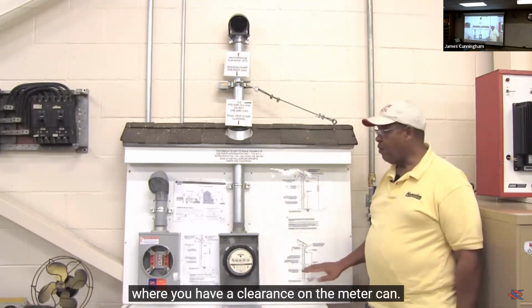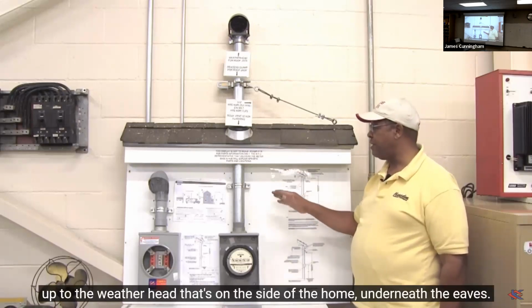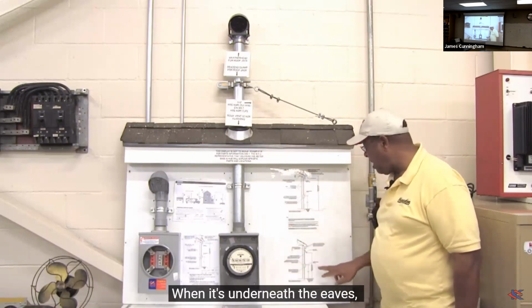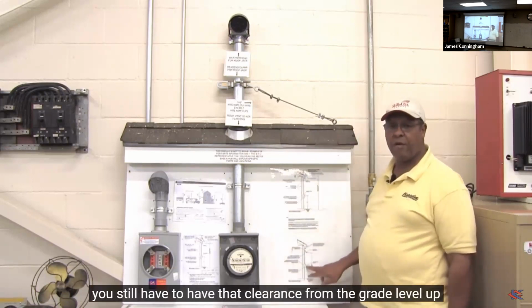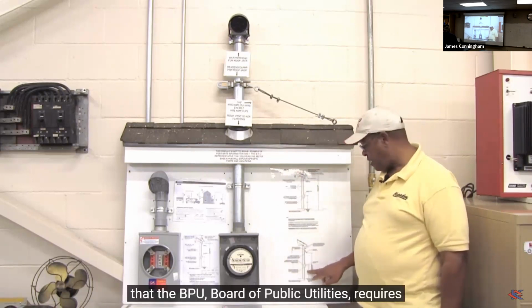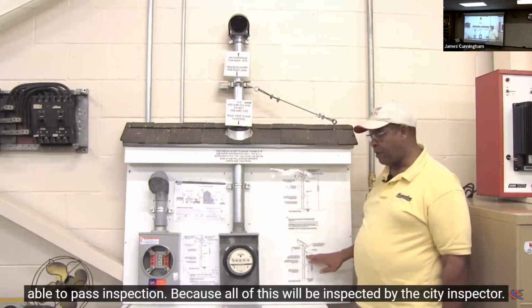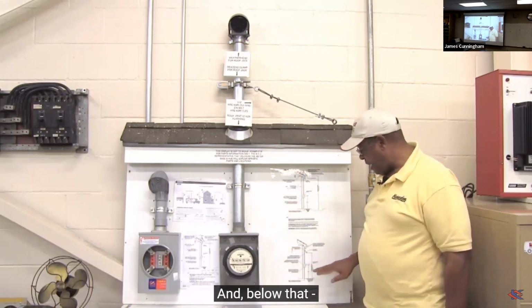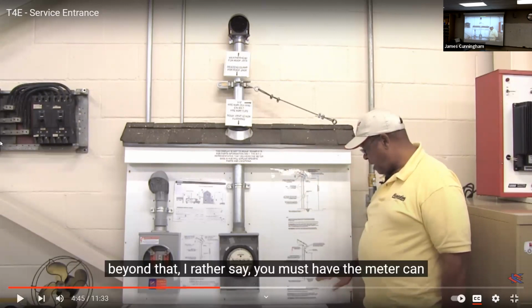Below here, you have a different setup where you have a clearance on the meter can up to the weatherhead that's on the side of the home underneath the eaves. When it's underneath the eaves, you still have to have that clearance from the grade level up that the BPU, Board of Public Utilities, requires in order for it to be able to pass inspection, because all this will be inspected by the city inspector. And below that, when you install the panel, there's a code of clearance, so you can't have a tree or a bush or something right in front of your electrical panel. You have to be able to service it in case of emergency, and it has to be a certain height off the ground to the center of the panel. Usually we shoot for about 4 feet to the center of the panel, and then part of it might be above that. It depends on the size of the panel though. So there is a code for both of those things.